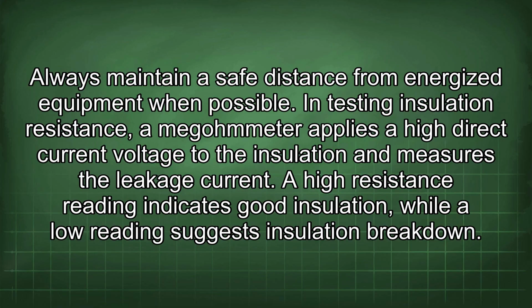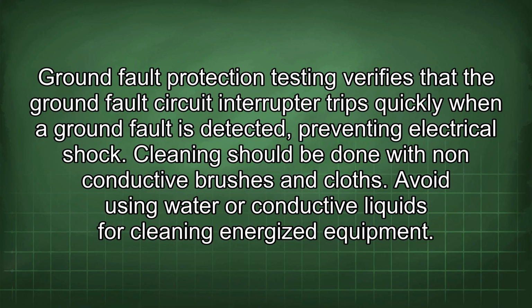In testing insulation resistance, a megohmmeter applies a high direct current voltage to the insulation and measures the leakage current. A high resistance reading indicates good insulation, while a low reading suggests insulation breakdown. Ground fault protection testing verifies that the ground fault circuit interrupter trips quickly when a ground fault is detected, preventing electrical shock. Cleaning should be done with non-conductive brushes and cloths.